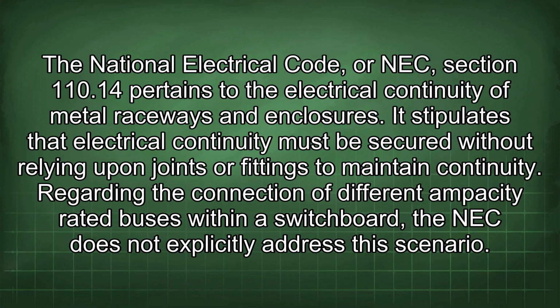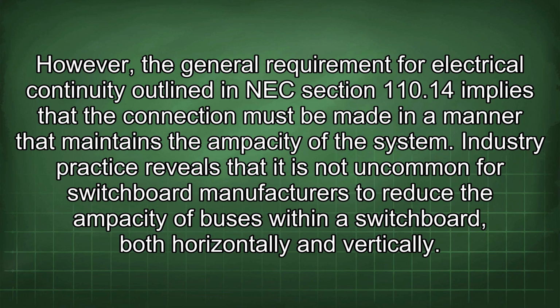National Electrical Code, or NEC, Section 110.14 pertains to the electrical continuity of metal raceways and enclosures. It stipulates that electrical continuity must be secured without relying upon joints or fittings to maintain continuity. Regarding the connection of different ampacity-rated buses within a switchboard, the NEC does not explicitly address this scenario. However, the general requirement for electrical continuity outlined in NEC Section 110.14 implies that the connection must be made in a manner that maintains the ampacity of the system.